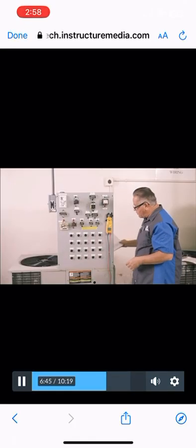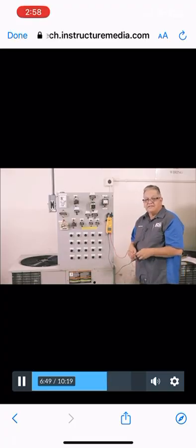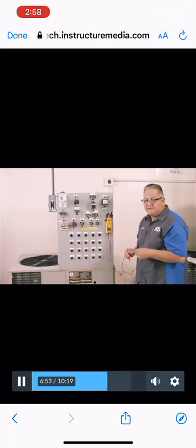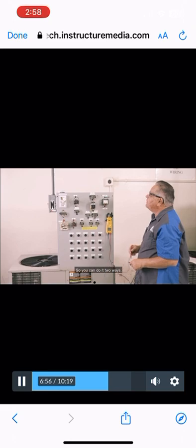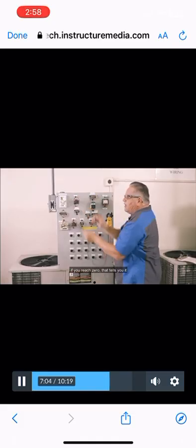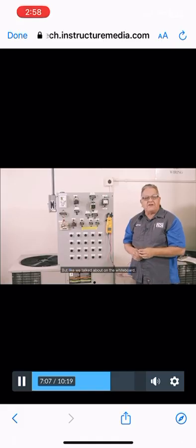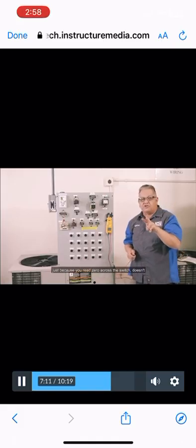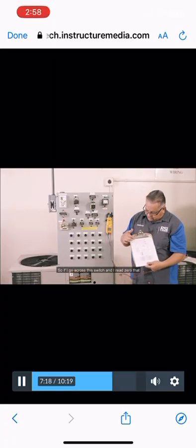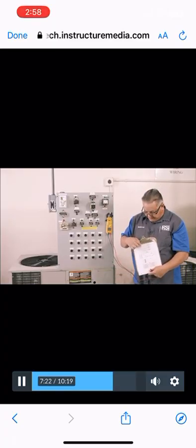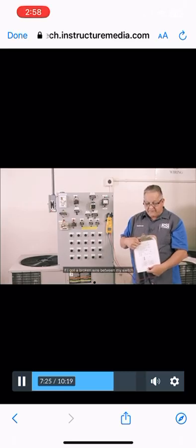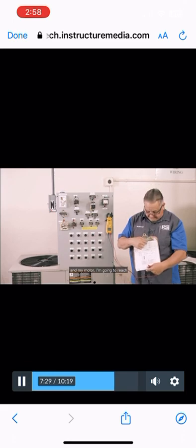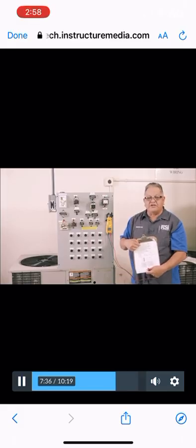Just because you got 24 to your coil doesn't tell you that that coil is good, because we got to check its job. Its job is to open and close switch. So let's check that switch. So you can do it two ways. You can go straight to the switch, and if you read 0, that tells you it should be closed. But like we talked about on the whiteboard, just because you read 0 across the switch doesn't mean it's closed. It should be closed. So if I go across this switch and I read 0, that tells me that switch should be closed. But if I got a broken wire, we talked about it the other day, if I got a broken wire between my switch and my motor, I'm going to read 0. If I got a broken wire between my line 1 and my switch, I'm going to read 0.